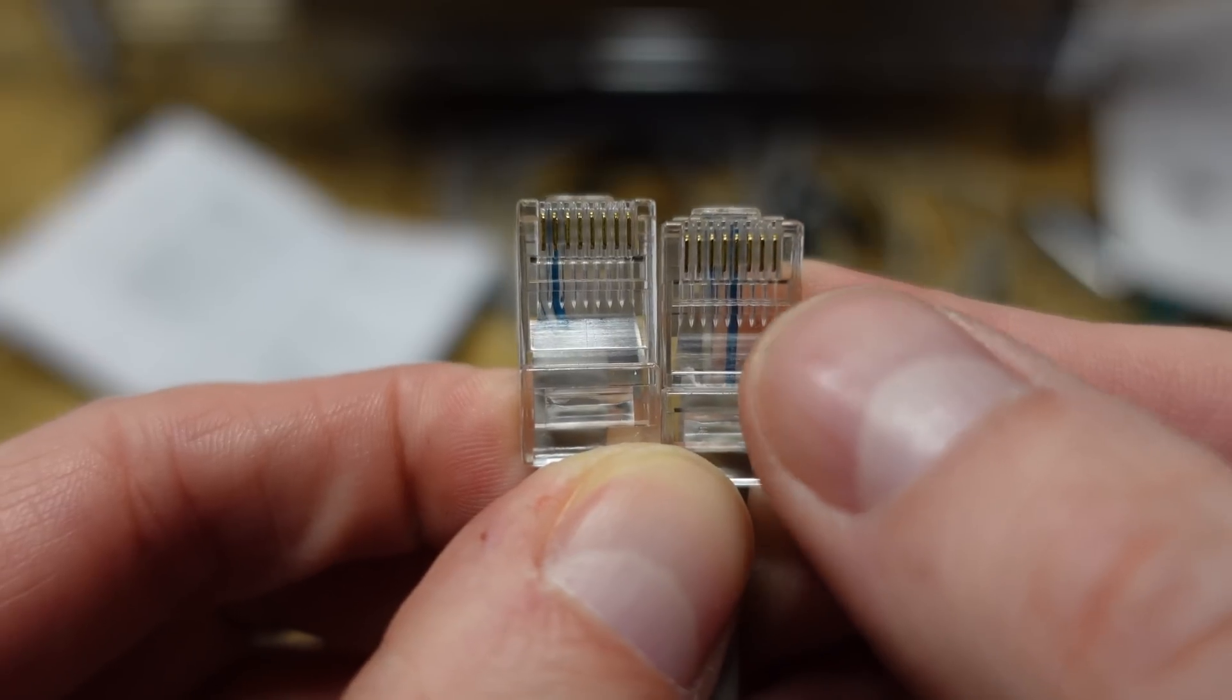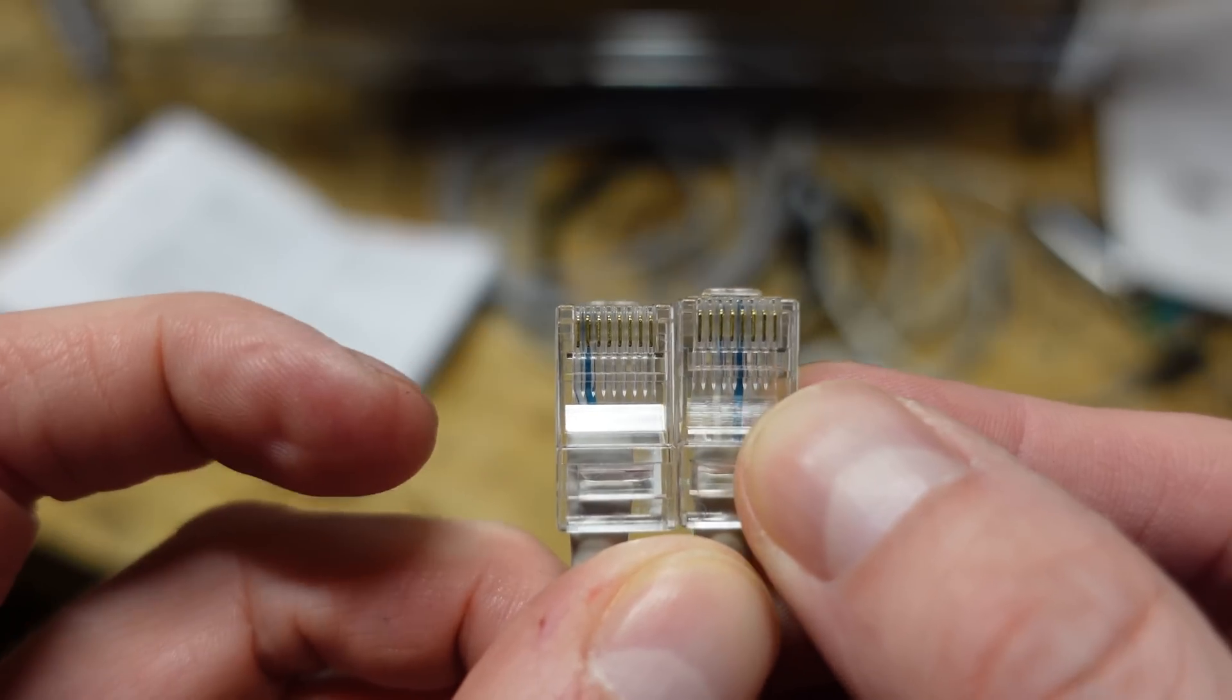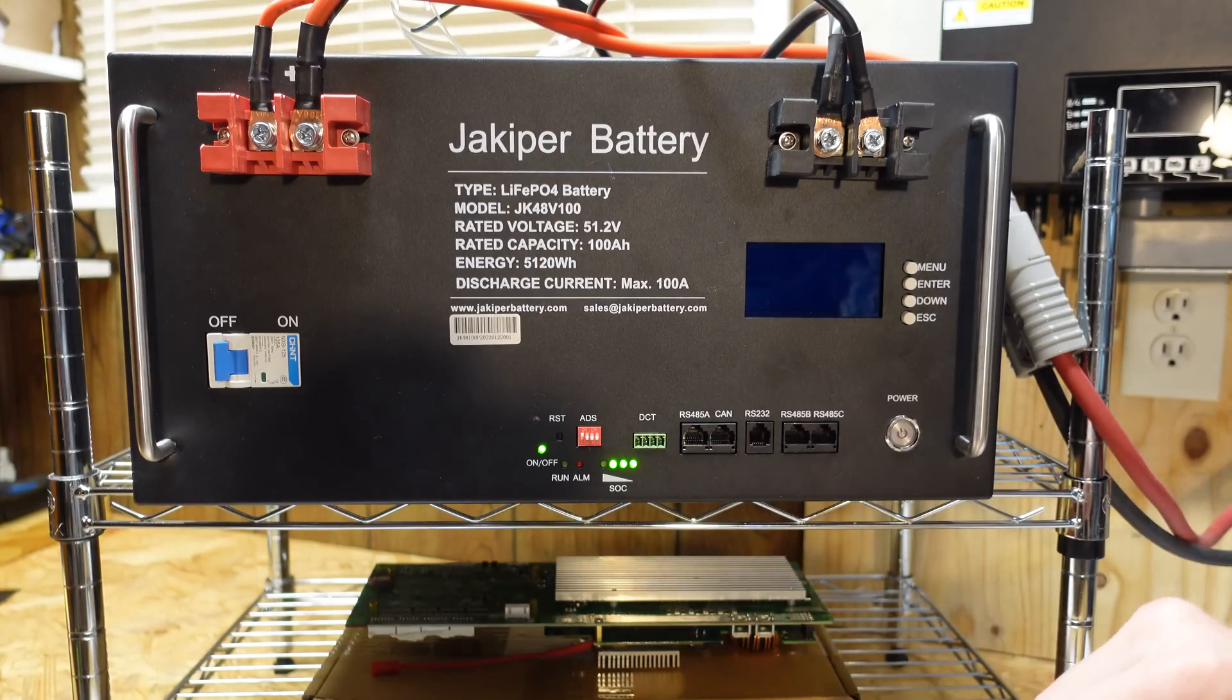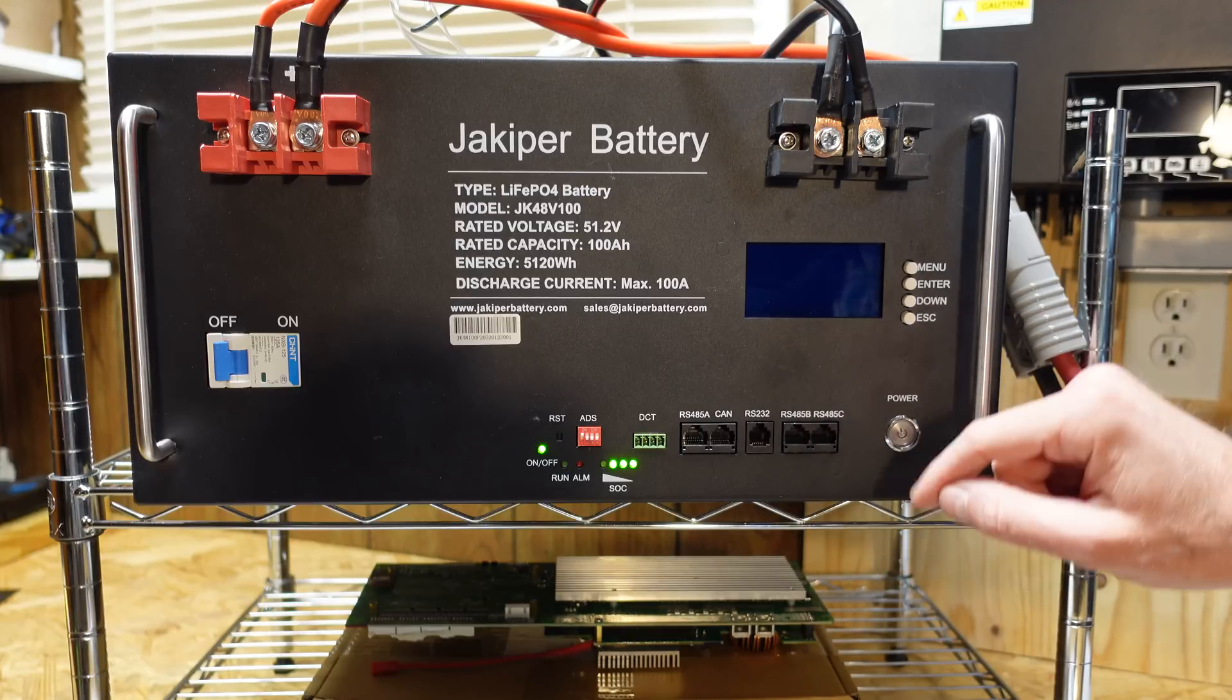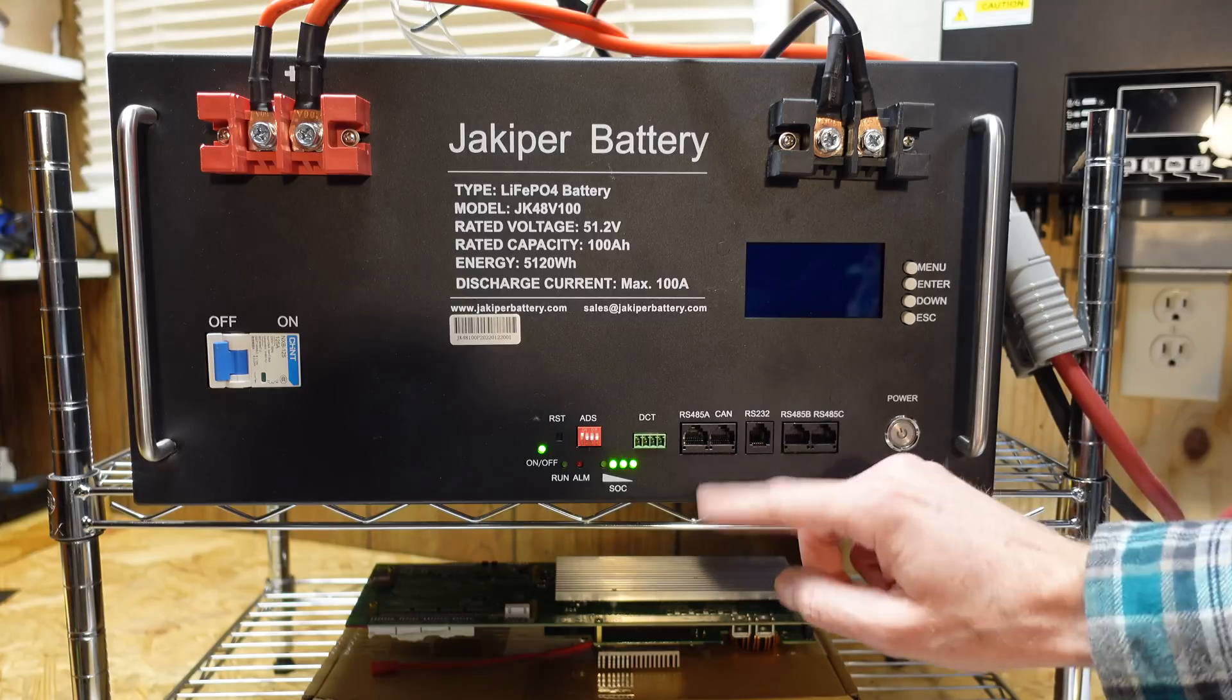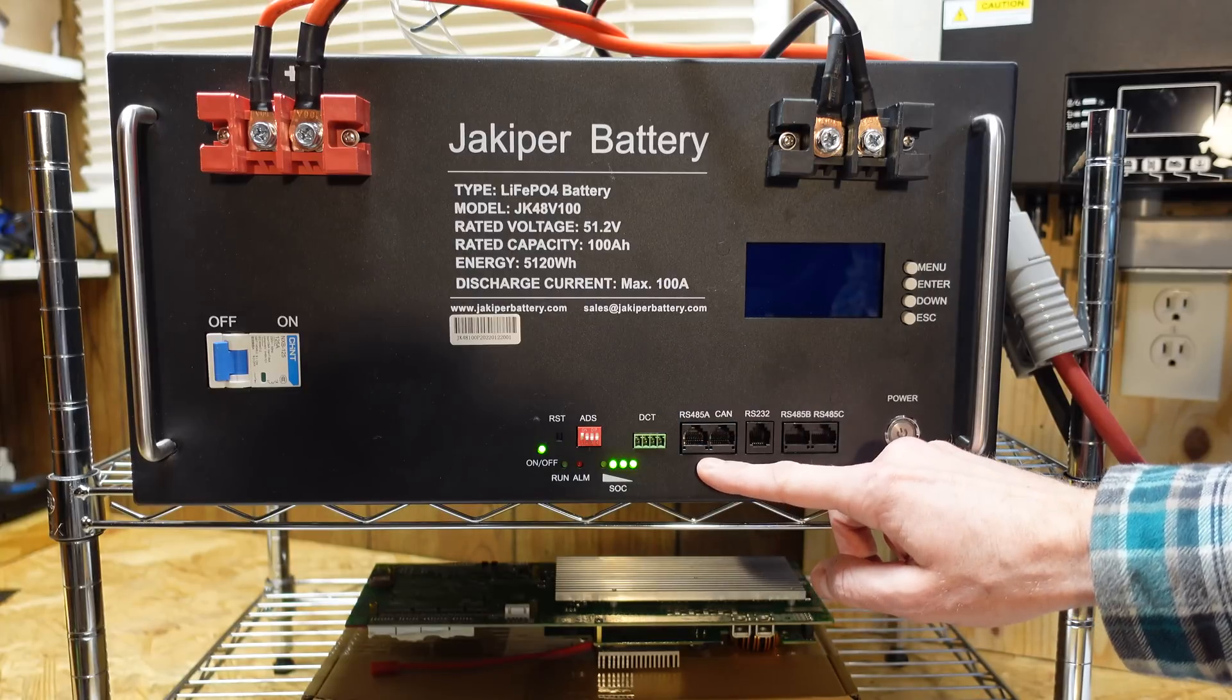So, on this cable, the right side goes in the inverter, the left side goes in the battery. We can see I've got pin number three or blue stripe going to pin number one, and we can see I've got pin number five or solid blue going to pin number two. Now, this battery does have three ports labeled RS-485. Ports B and C are for communications from battery to battery, and these two ports are simply cross-through ports on the inside of the battery, so it doesn't matter if you use B or C. The port labeled RS-485A is using a completely separate protocol, and it appears to me to be a separate bit rate. This port is supposed to be 9,600 baud rate.